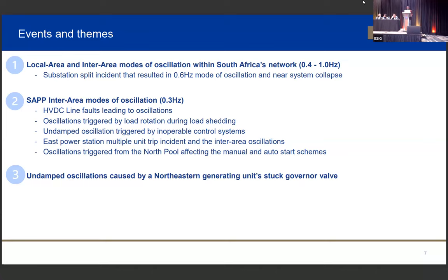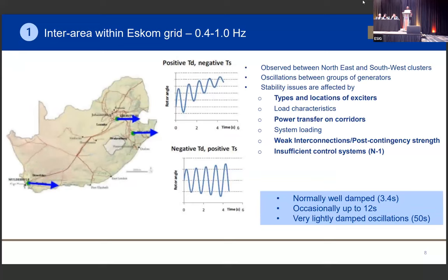The third one was an undamped oscillation caused by a unit that had a stuck governor valve. Generally, this mode of oscillation is within South Africa, but it's inter-area. The group of generators in the Northeast tend to oscillate, if triggered, against the group of generators in the South, Southwest. They're normally well damped, especially after the recent strengthening where we paralleled 765 kV from the north to the south. It helped a lot in strengthening this mode. But the locations of exciters, power transfer on corridors, weak interconnections, and insufficient control systems are the ones that affect this mode a lot.